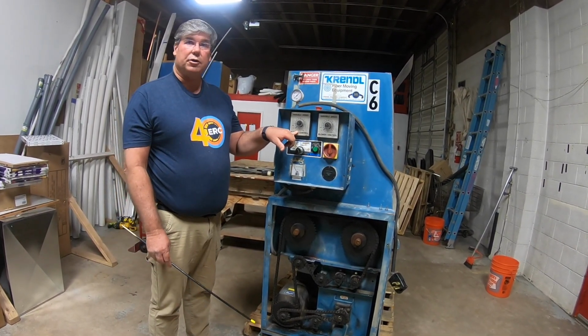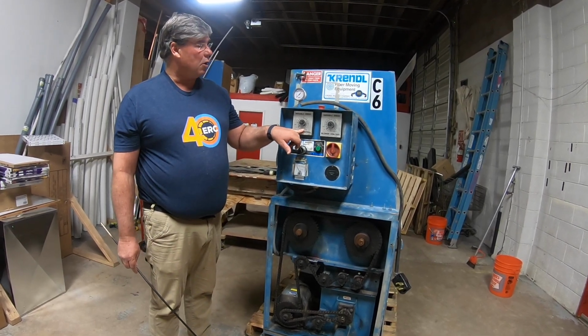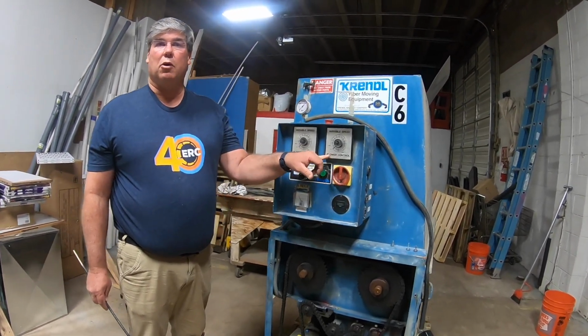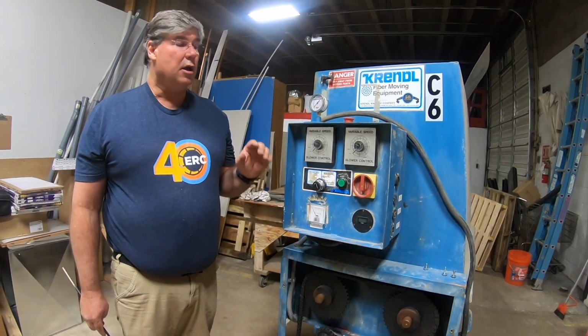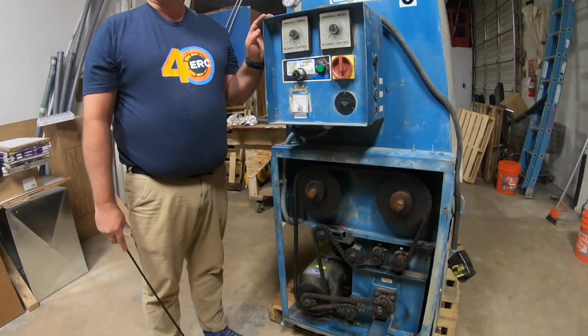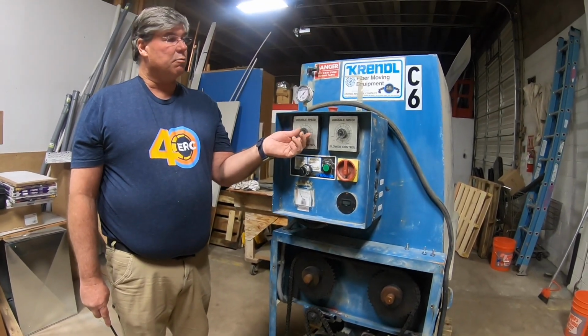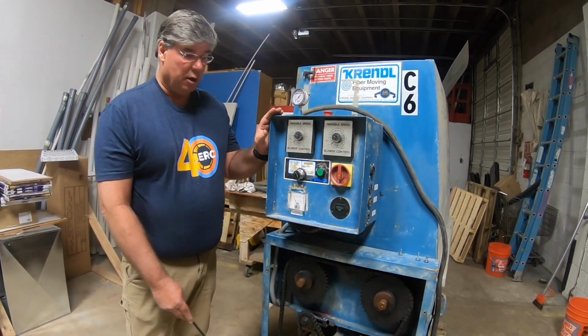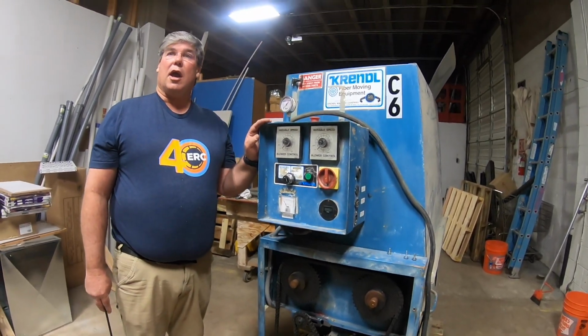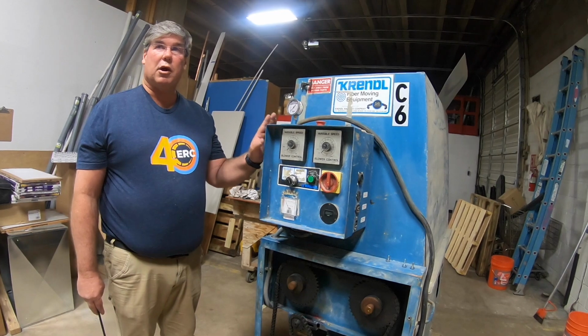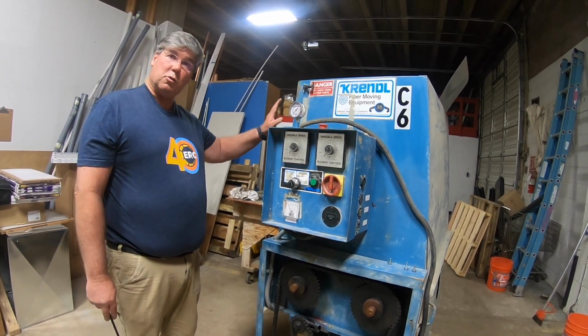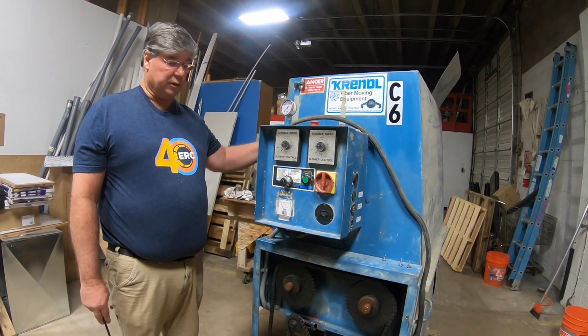One of the things I want to point out is that before I test the pressure there, I turn on one of these blowers at a time to make sure both blowers are turning and putting out air. You can measure their pressure down there if you'd like. Then you can turn them both on to where you normally have them set, measure the pressure again, and that will give you an idea if you're having problems with the blowers on top, which are the ones on the back where the filter was.